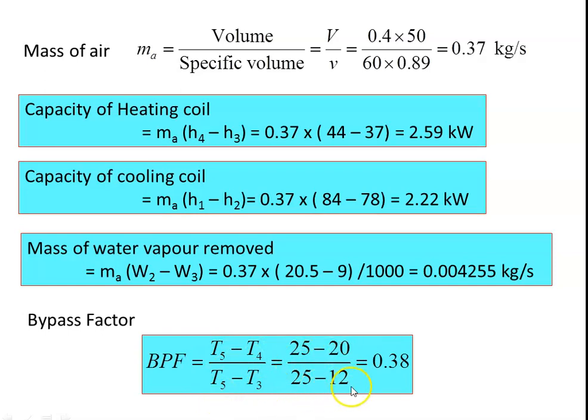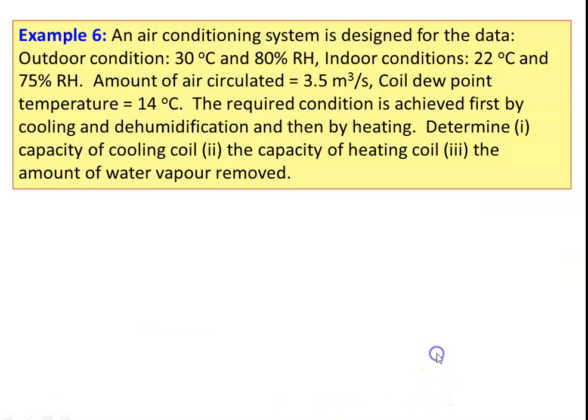Calculating the bypass factor: (25 − 20) / (25 − 12) = 5 / 13 ≈ 0.38. Bypass factor is approximately 0.38.